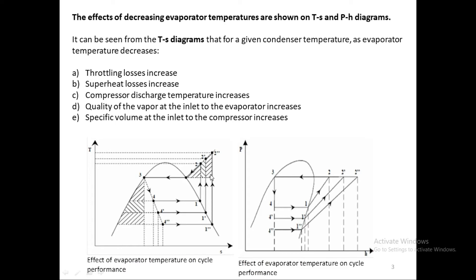The superheat loss also increases on the compressor side. Before, the compressor compressed from state 1 to the condenser pressure, but if we lower the evaporator pressure, it must go from a much lower pressure to a much higher pressure, reaching a much higher temperature. This extra heat must be rejected in the condenser environment. We supply the compressor extra energy to compress it, and then we waste that energy because we don't need this extra heat. The compressor discharge temperature therefore increases.